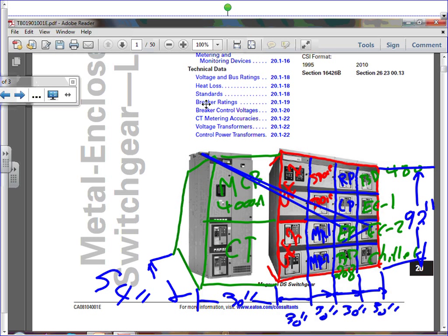Any comments, guys? Any questions about the switch here? So to summarize, we have panel boards. Andrew, my friend, we have panel boards that can go all the way up to 1200 amp. Higher than 1200 amp, I have two options. Switchboard, the poor man's option, can go all the way up to 5000 amp. Typically 4000 is what we use. They're not draw out typically. And there's a switchgear that can go all the way also up to 5000 amp. Typically we cap them at 4000 amp.